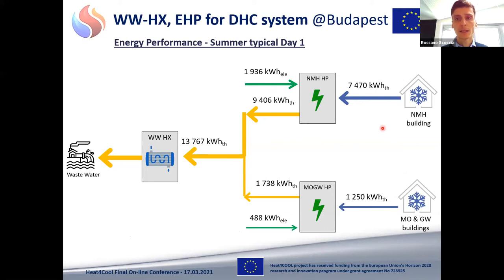In this case, it's a summer typical day, so we produce cooling energy for the new market hall and for the other two buildings of the municipality, for a total of around 9,000 kilowatt hour of cooling energy produced by two chillers. And these chillers then throw away this thermal energy got from the buildings thanks to this wastewater heat exchanger. The wastewater heat exchanger has a so-called clean water side, which is this side, which is linked to the chillers, and the wastewater side, which is this side on the left.